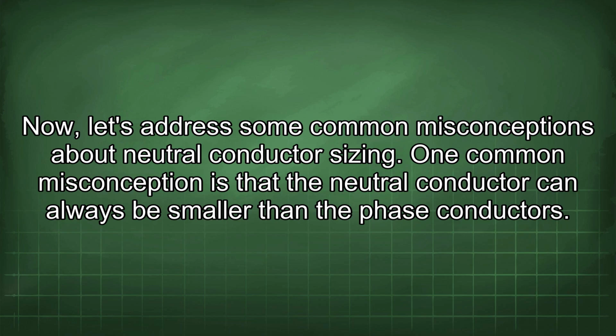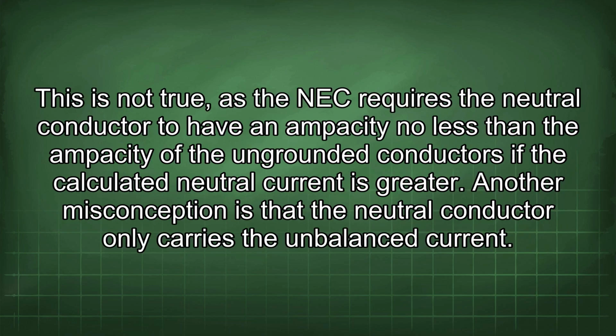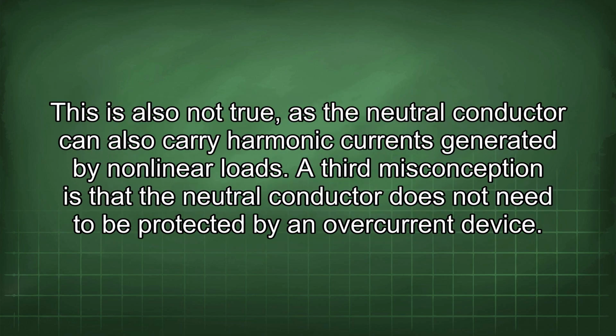One common misconception is that the neutral conductor can always be smaller than the phase conductors. This is not true, as the NEC requires the neutral conductor to have an ampacity no less than the ampacity of the ungrounded conductors if the calculated neutral current is greater. Another misconception is that the neutral conductor only carries the unbalanced current. This is also not true, as the neutral conductor can also carry harmonic currents generated by nonlinear loads.